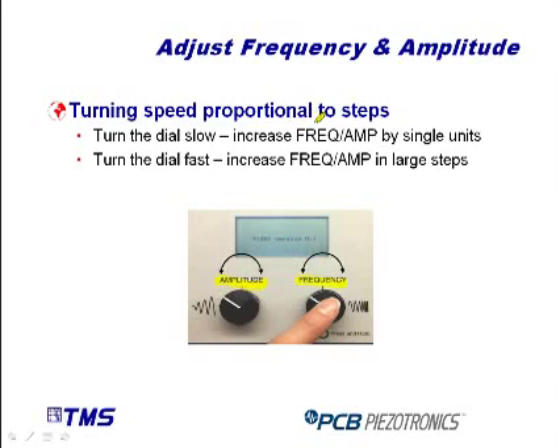In addition, we have some smarts. As you turn the dials, the faster you turn the dials, the larger the steps of the increments that you see on the display. So if you turn the dials very slowly, you'll be able to feel the detents in the dial, and you'll be able to change the amplitude and frequency settings by single units. But if you rotate those dials quickly, you'll be able to make large steps to go from, for example, 7 hertz up to 10 kilohertz very quickly.